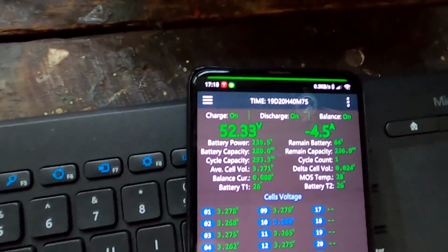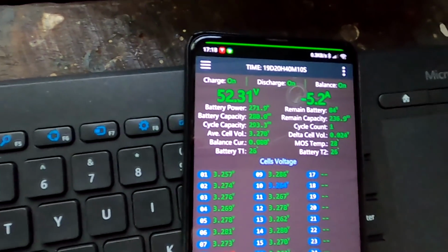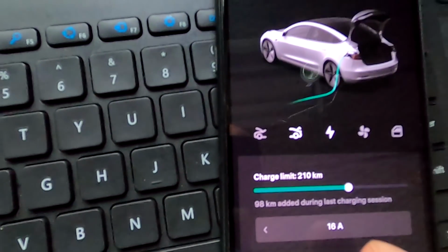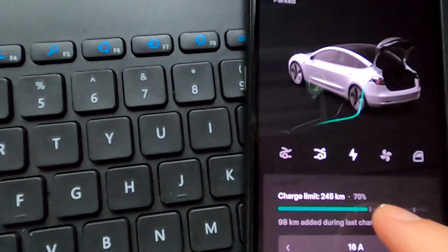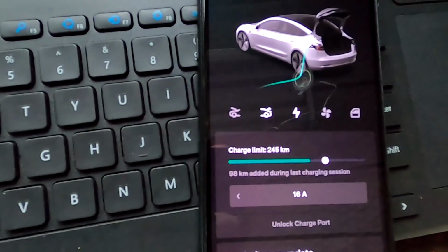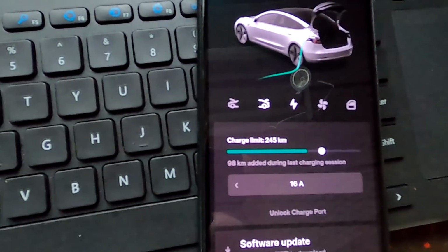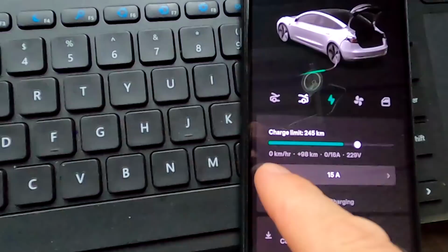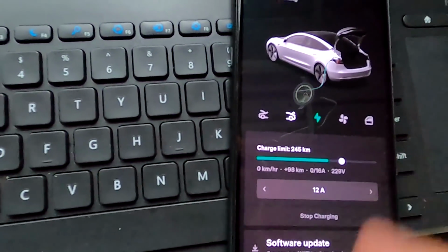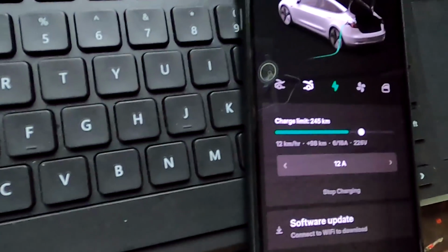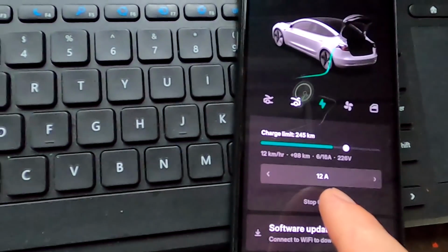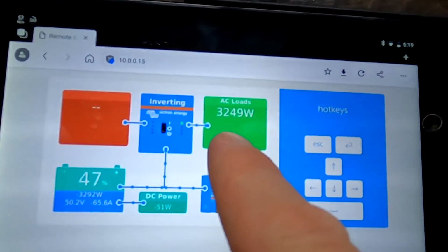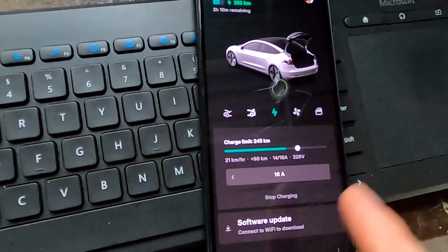Very cool! Okay, so minus 4.5, minus 5 amps are coming from this battery now. Now what we are going to do is set this one to 70% and start charging with 16 amps. I like this because both inverters will kick in after a while. It's so cool, sits on 16 amps. I'll go a little further down to maybe 12 first to check on the current. So 12 amps would mean 3.2 kilowatts. Okay, I think we can go all the way to 16 amps, that's the maximum we can charge here.